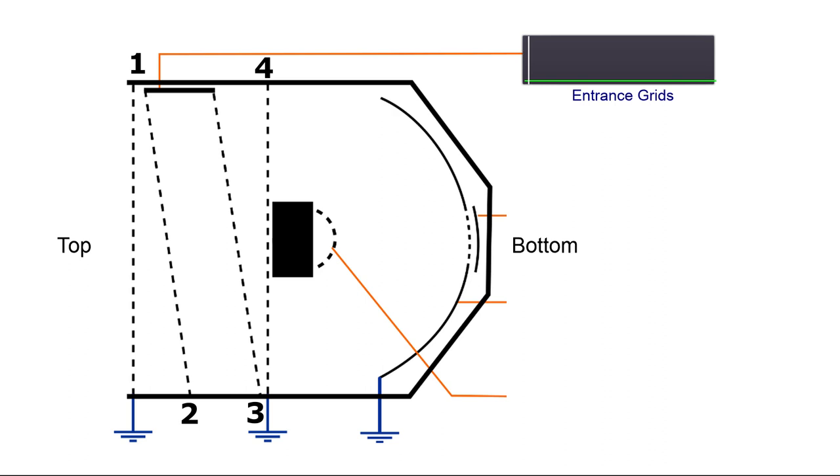At the top of the bucket are four metal grids. The first and last are connected to electrical ground, and the middle two are connected to each other, and then to a signal amplifier.